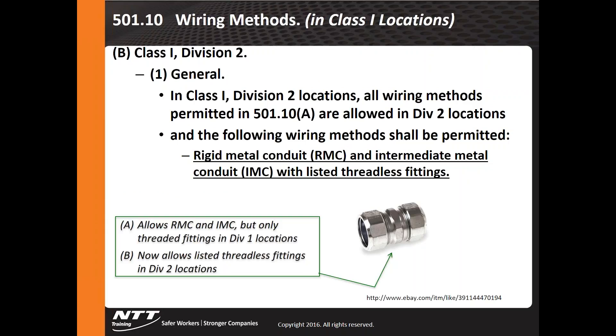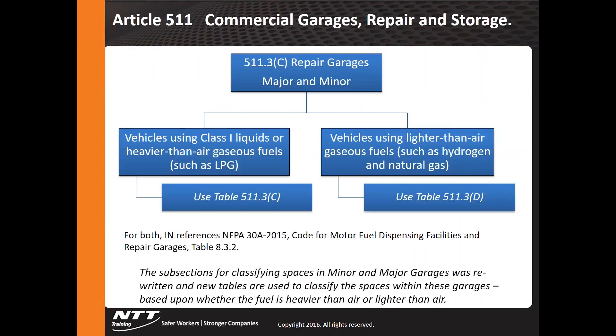In Article 501, Section 10 — for Class 1, Division 2 locations, which involve temporary exposure to gases and vapors, they are now allowing a slip-type fitting, often called a compression fitting, rated for use with RMC and IMC. Previously, Class 1 Division 1 full-time exposure required only threaded couplings with RMC and IMC. This new compression-type fitting is allowed, but only in Division 2 locations.